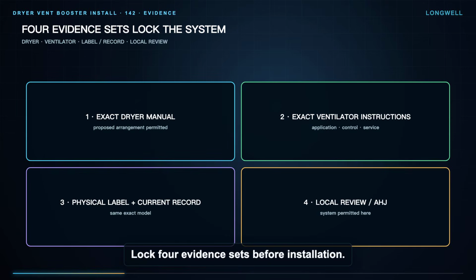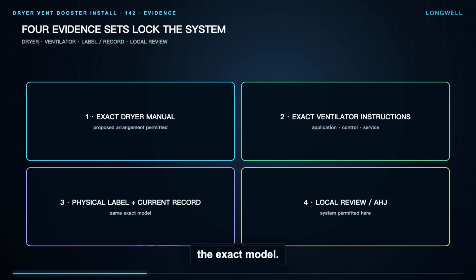Lock 4 evidence sets before installation. First, the exact clothes dryer manual must allow the proposed arrangement. Second, the exact power ventilator instructions must define the permitted application, controls, placement, service, and maintenance. Third, the physical product label and current certification record must match the exact model. Fourth, local requirements and the authority having jurisdiction must permit the system. If one item is missing or contradictory, the installation remains unresolved.